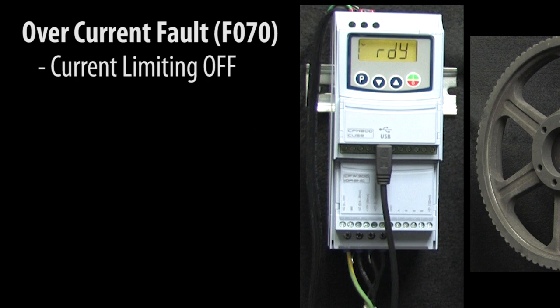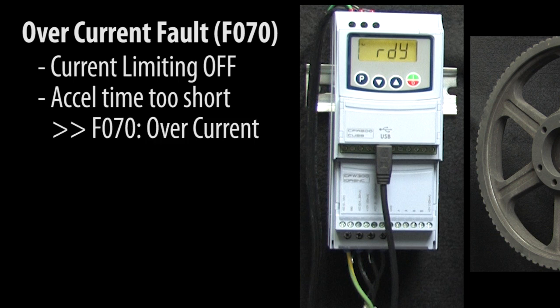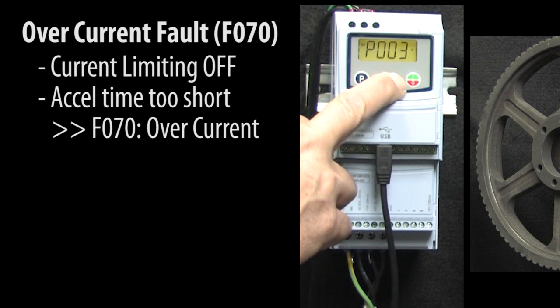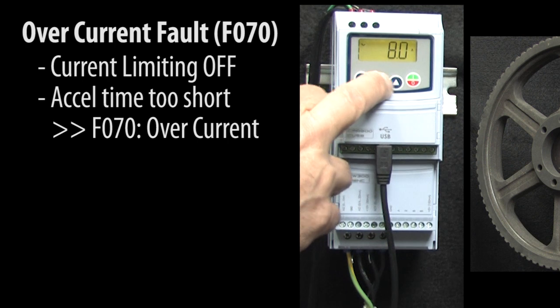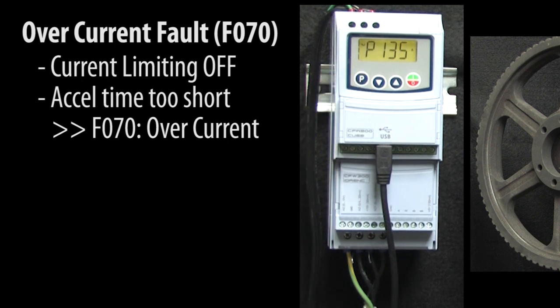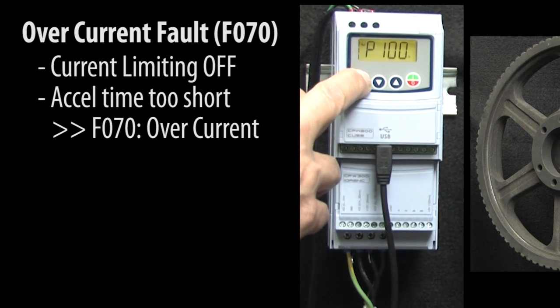But if you turn that current limiting function off and enter a really short acceleration time, you will get an overcurrent fault. Let's try it. I'll go to the current limiting threshold in parameter 135 and set it to a big number, and that will disable current limiting. If we go to parameter 100, we see we still have a really short acceleration time, so that's fine.